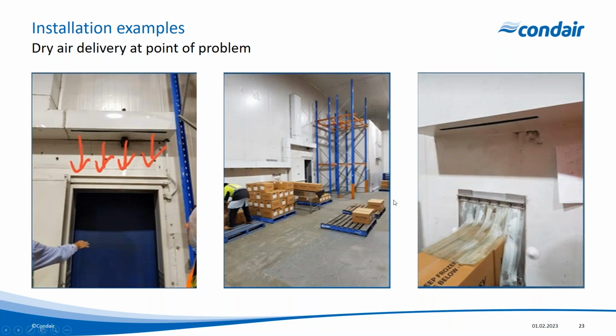And this one was quite interesting. Actually, we've got 2 doors. It's got the main door to the cold store, but they'd also got a conveyor door where we got a constant feed of goods coming out when it was in production. And so we got a further airline, so it's coming down from the dehumidifier going right, and it's going left, and that left duct is going to this conveyor opening. And again, we're putting dehumidified air down over that opening to prevent ice build up on that strip curtain and preventing that strip curtain being ineffective in clinging together.